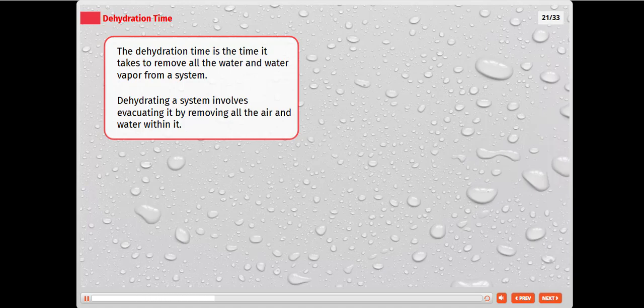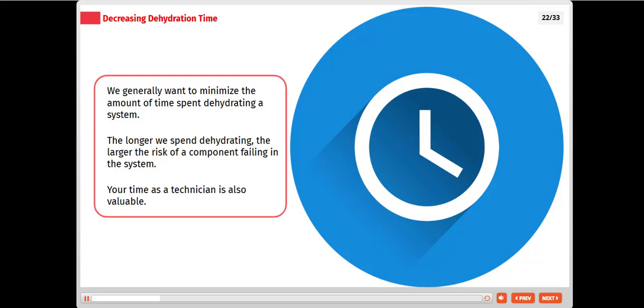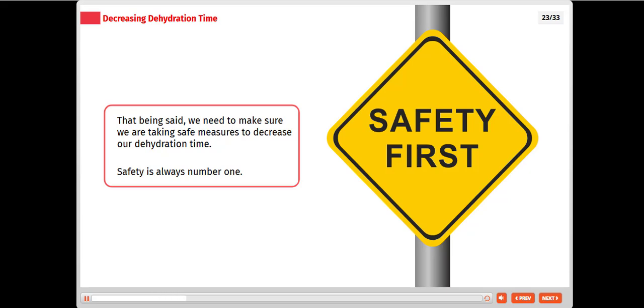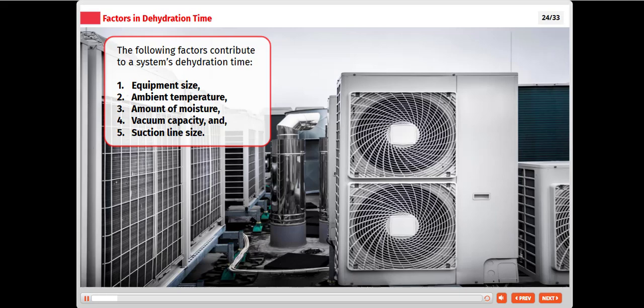Dehydrating a system involves evacuating it by removing all the air and water within it. We generally want to minimize the amount of time spent dehydrating a system. The longer we spend dehydrating, the larger the risk of a component failing in the system. Your time as a technician is also valuable. That being said, we need to make sure we are taking safe measures to decrease our dehydration time. Safety is always number one. The following factors contribute to a system's dehydration time: equipment size, ambient temperature, amount of moisture, vacuum capacity, and suction line size.